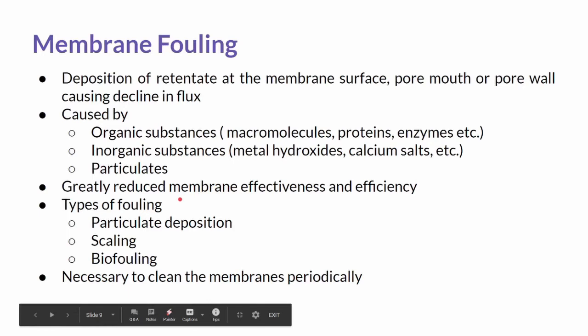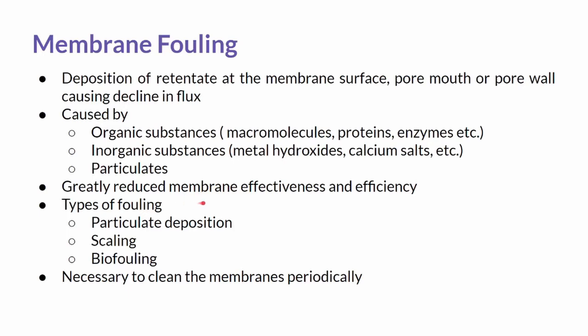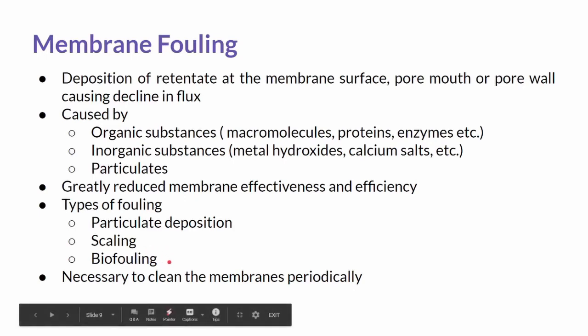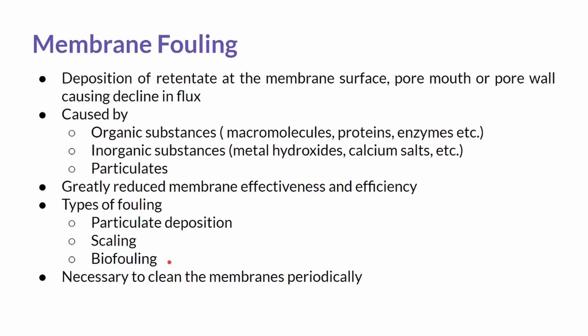Moving on to the types of fouling, we mainly have three types. Firstly, particulate deposition which refers to the standard blocking of molecules on the pore walls, pore mouth, or the formation of cake layers. Then we have scaling, which is a result of concentration polarization on the membrane surface due to which precipitation occurs. These inorganic salt deposits block the pores causing a decline in the flux. Then we have biofouling where microorganisms adhere to the membrane surface forming a gel which is often called biofilm. These are mostly seen in biological equipment or terms related to biology.